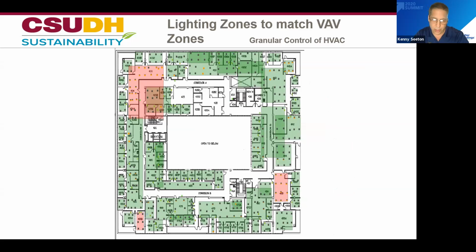If you look, you can see a bunch of square blocks. In a sense, that's a VAV zone. The VAV is the valve that opens and closes to let air into individual spaces. In a perfect world, everybody gets their own VAV. In the real world, classrooms get their own VAV, and presidents and vice presidents too, but office people have to share a VAV—3, 4, 5, sometimes 6 offices sharing one zone.